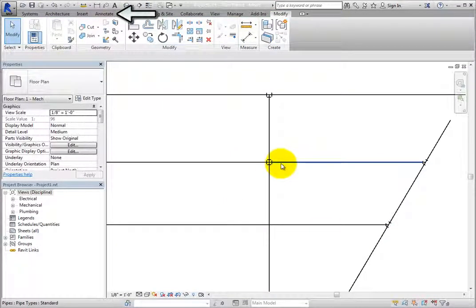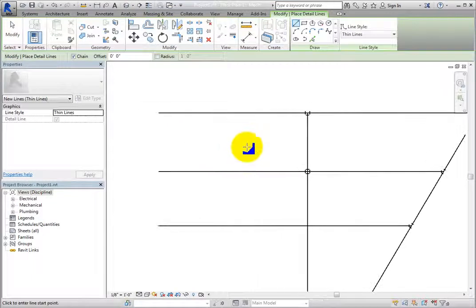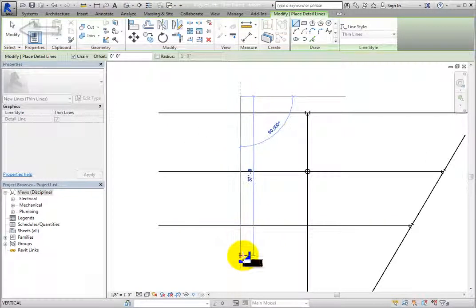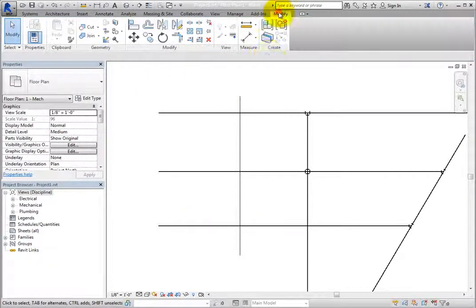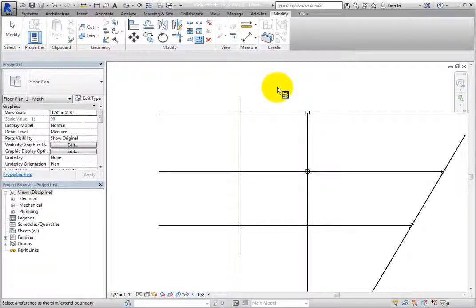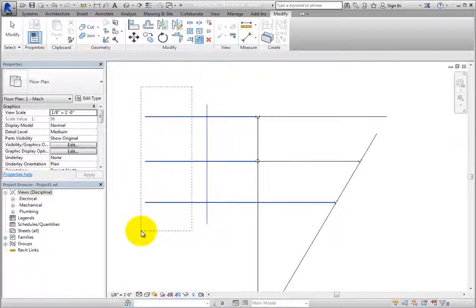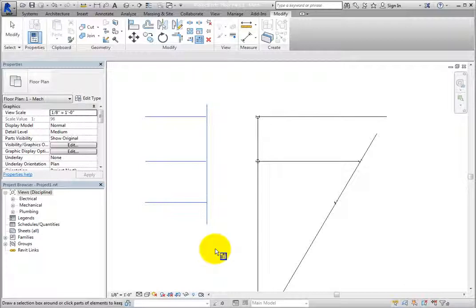Switch to the Annotate ribbon and start the Detail Line tool from the Detail panel. Sketch a vertical line to the left of the vertical pipe, then click Modify to end the command. Switch back to the Modify ribbon and start the Trim-Extend Multiple Elements tool. With the tool active, select the Detail line as the reference. Then use a crossing window to select each of the horizontal pipes on the left side of the Detail line — remember, you select the portion of the element that you want to keep. Once you do, the pipes are trimmed back to the location of the Detail line. However, the fittings remain the same and do not update for the removal of the pipes.